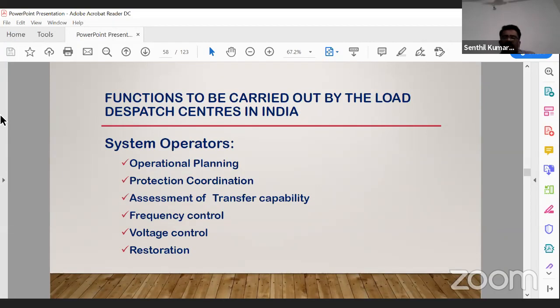What is the assessment of transfer capability? It means we calculate the transmission availability. There are a lot of transmission lines - above 110 kV is the transcom level, below 110 kV down to above 66 kV is the DISCOM side, and above 66 kV is the transmission perspective. So we have to calculate how much power flow is possible or can be transferred from one place to another. For example, if I am in Chennai and need 100 megawatts of power, how am I getting that power? First we need to find out what transmission lines are available and what their transmission capacity is. These calculations are part of the assessment of transfer capability.